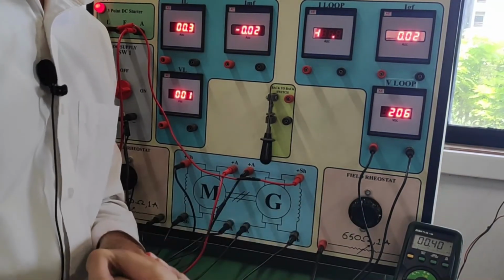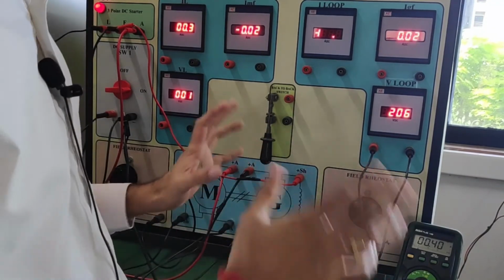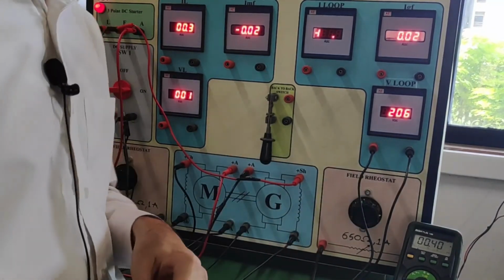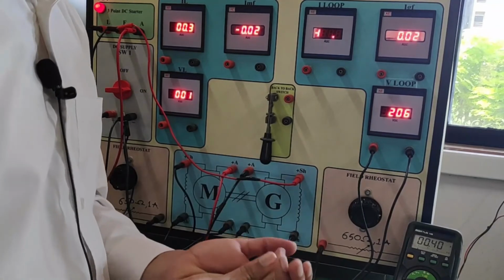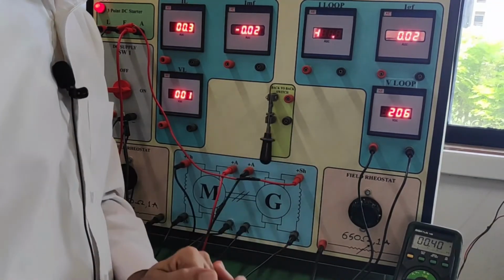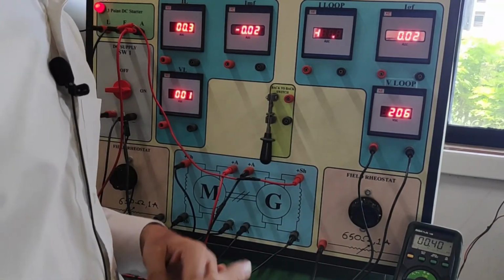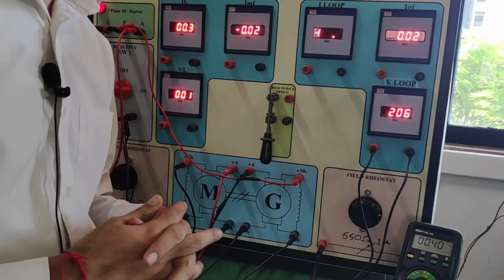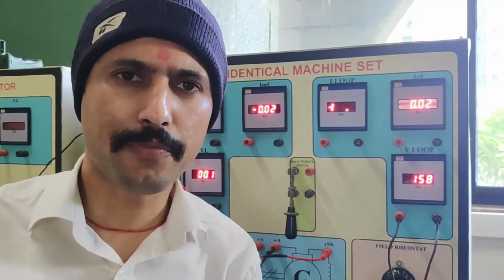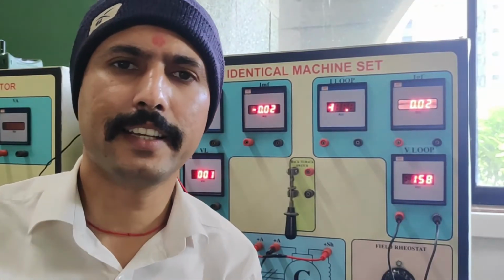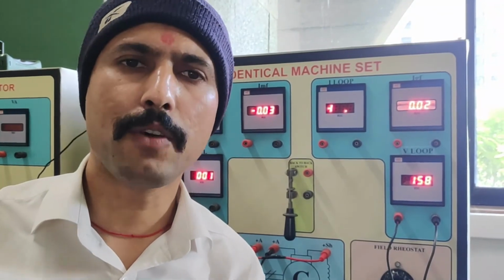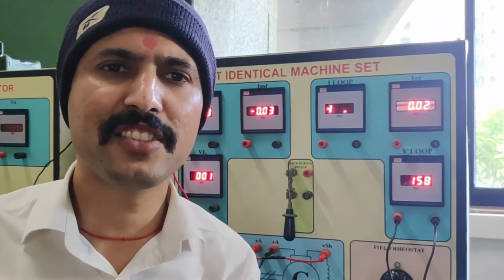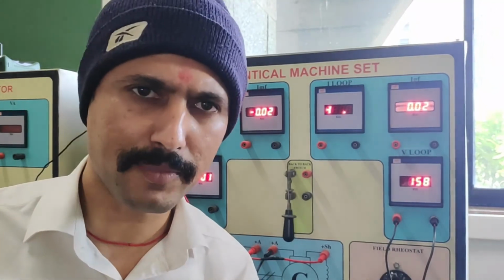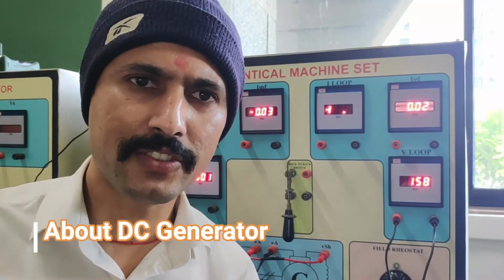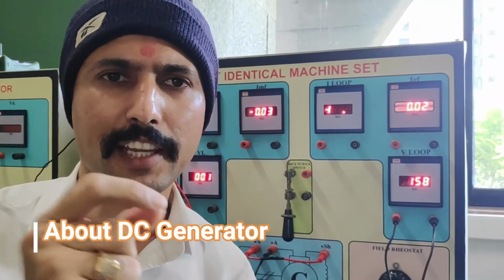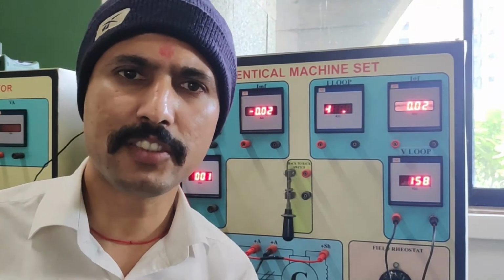The rated voltage of this machine is 220, so we'll perform this experiment up to here. So the field current is 0.4 ampere and the terminal voltage we are getting is 206. We have performed this experiment at 1350 rpm. Now what we will do is change the speed and perform the same thing. And why are we doing this? To understand one of the very important things about the DC motor.